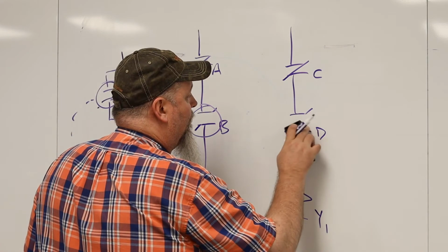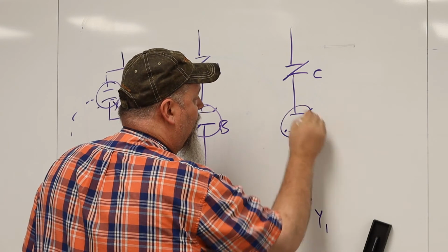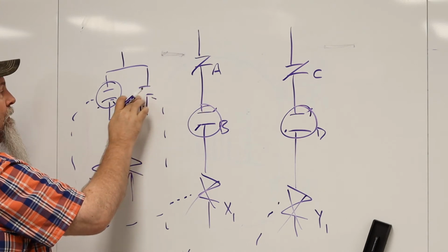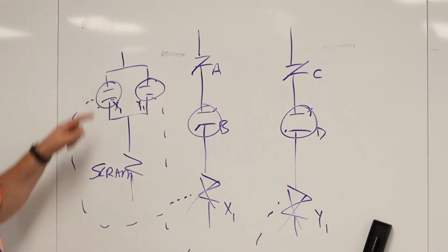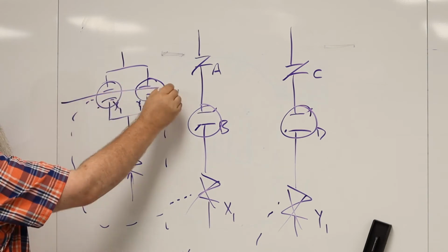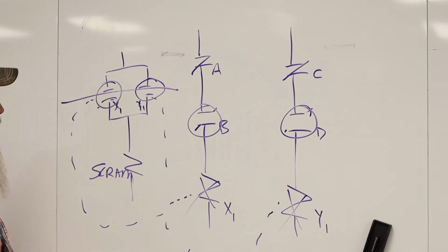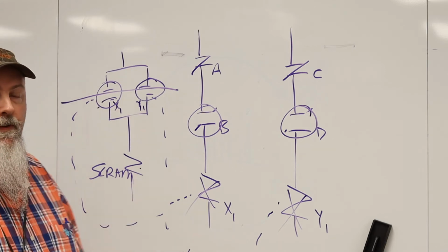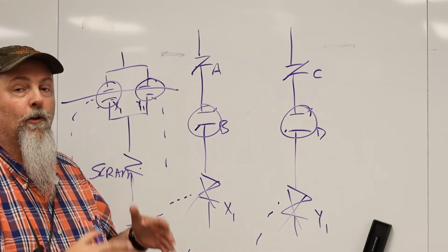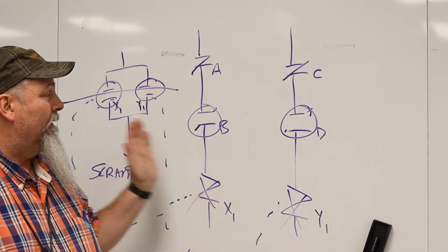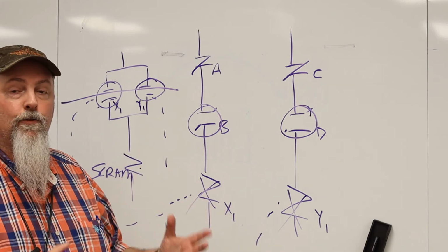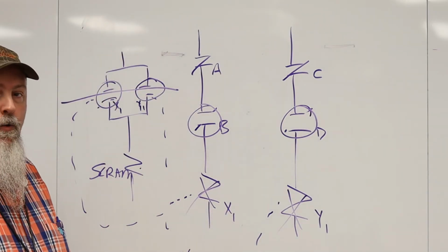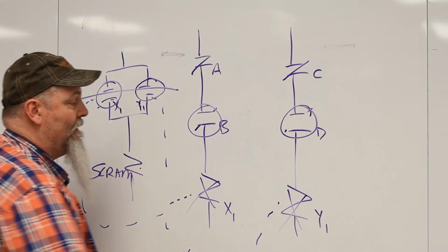And then, if I also get delta, then the Yankee 1 is de-energized. And now I've cut off power to the scram relay. The scram relay de-energizes, and whatever valves it was keeping open or keeping closed, they open up and allow and drive the control rods in. So that's a 1 of 2 taken twice, showing both energized to actuate and de-energized to actuate.